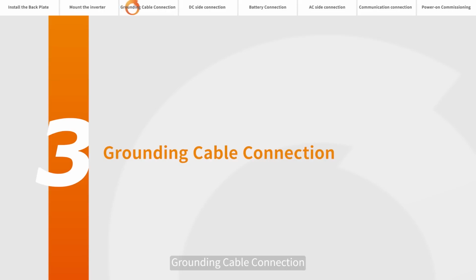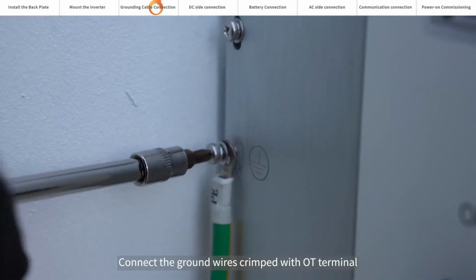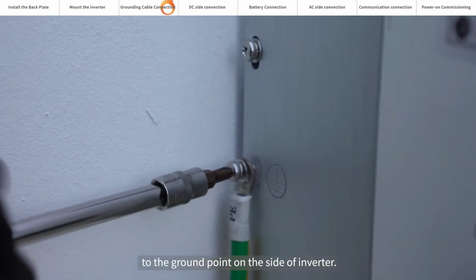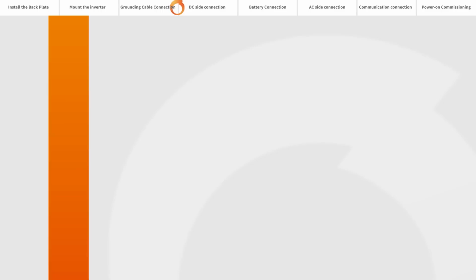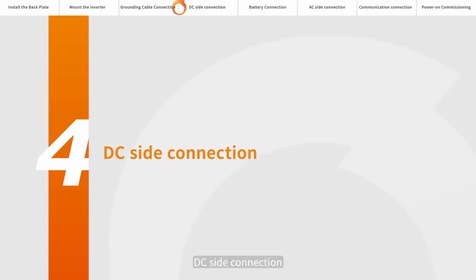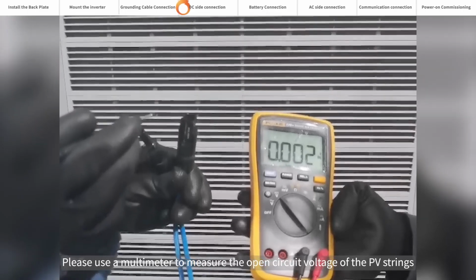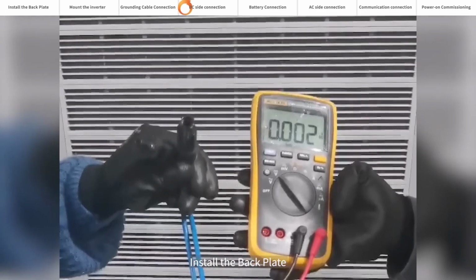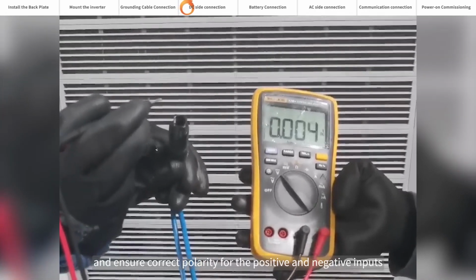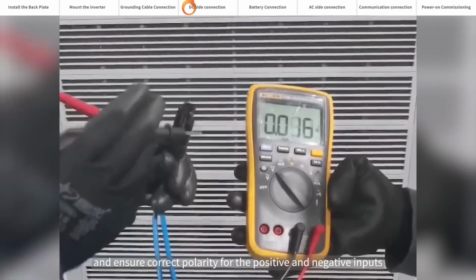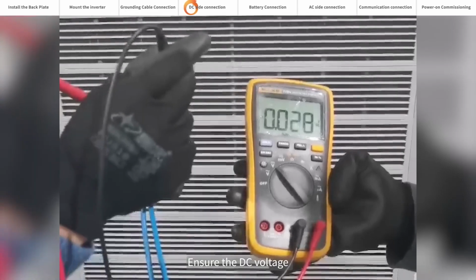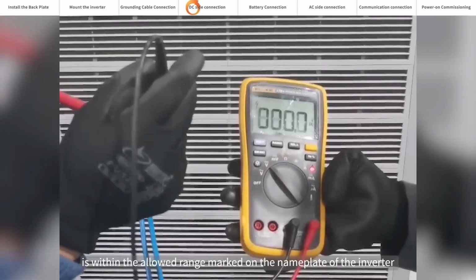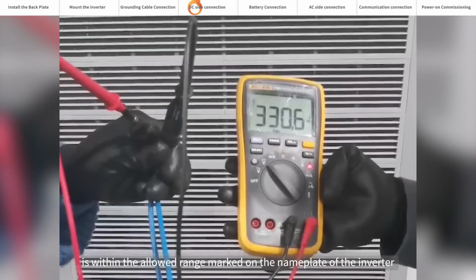Grounding cable connection. Connect the ground wires crimped with OT terminal to the ground point on the side of the inverter. DC side connection. Please use a multimeter to measure the open circuit voltage of the PV strings, and ensure correct polarity for the positive and negative inputs. Ensure the DC voltage is within the allowed range marked on the nameplate of the inverter.